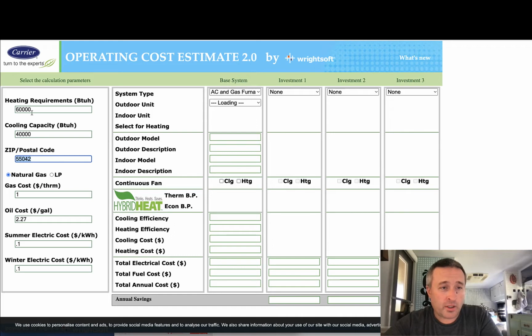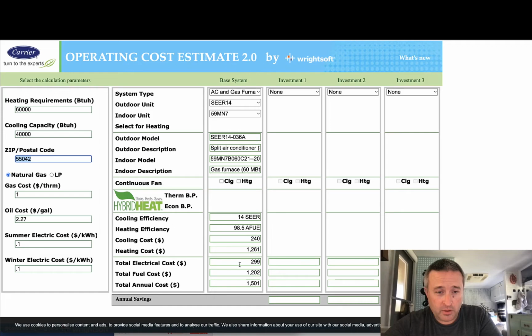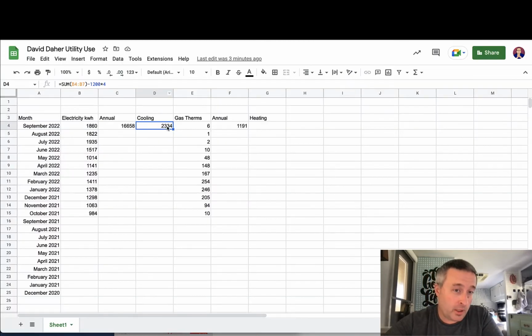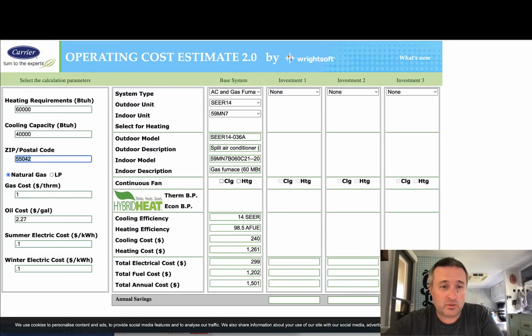So I'm just walking these into where I want them to be, and we're at 1,200 therms here, total fuel cost 1,200 and cooling cost 240. This is again at 10 cents a kilowatt hour, so that's 2,400 kilowatt hours and 1,200 therms, and we are at 2,300 and change and 1,200 therms - close enough for government work. Once you get within half a size, who cares - if you're within 6,000 BTUs, it's fine.